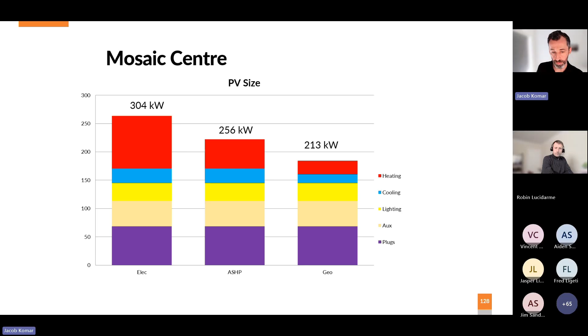With just electric strip heating, it would have been $900,000 with solar. With the Geo, it's $300,000 less than that. The cost premium to go to Geo was about $80,000, but you can see the cost difference even in this theoretical air source heat pump scenario is $130,000. It's always going to be cheaper to install Geo and get to net zero with Geo versus almost any other system, because you can reduce your solar costs. We wouldn't actually have had room on the roof to install solar except with the Geo option, because it reduced the demand so much.